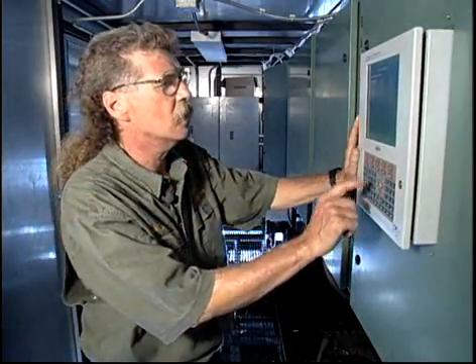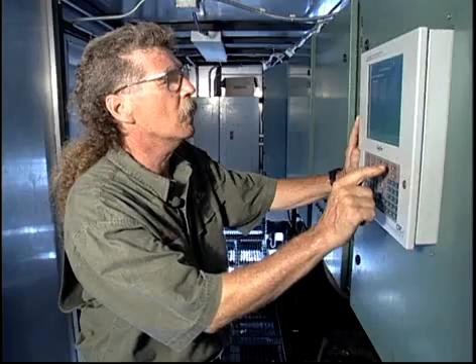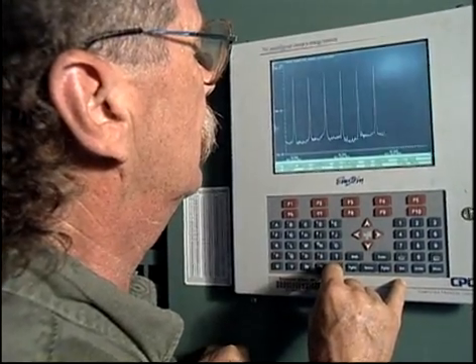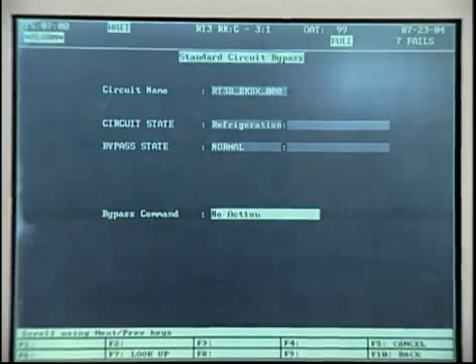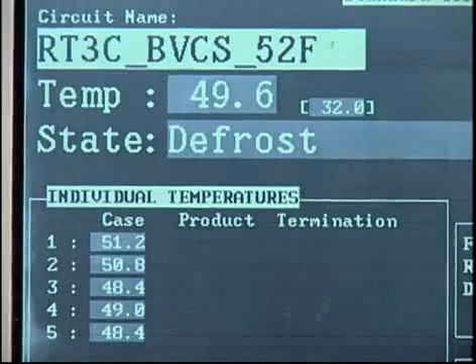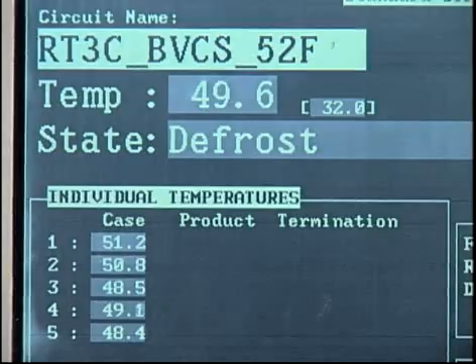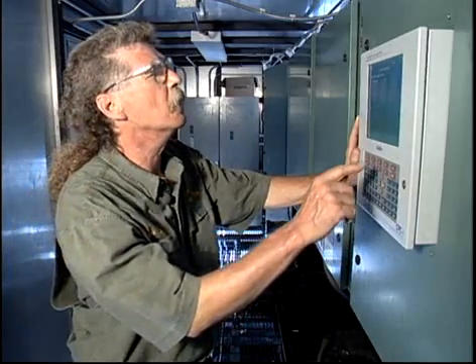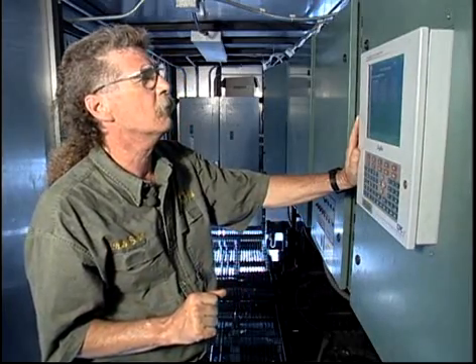This CPU controls things such as the defrost cycle and monitors for faults indicated by extreme pressure changes. It affords the technician a quick overview of the status of every operational cooling facility connected to it. Defrost is critical — you have to defrost the unit, but in such a fashion as to not jeopardize the freshness of the product. All defrost cycles are scheduled by the microprocessor and timed for a predetermined length, but sensors will override and terminate the time cycle if the evaporator defrosts sooner. This controller is like the nerve center for the whole cooling operation.